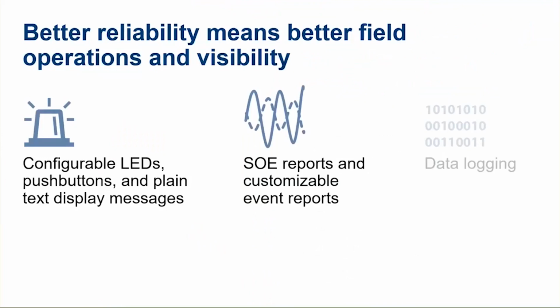Another thing to provide a reliable solution is to give you really good visibility as to what the problem is when you come on site and you're troubleshooting a station. So not only do we have configurable LEDs, push buttons, and plain text display messages so that it can give you good visible indication as to what's happening and what needs to be addressed to get that station back up and running. We also have things called SOE, which is sequence of event reports with timestamps to the millisecond, as well as data logging within the device. And I'm going to talk a little bit more about what that looks like as we go through this presentation.